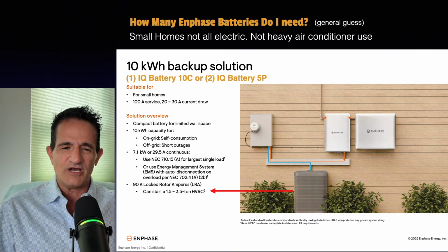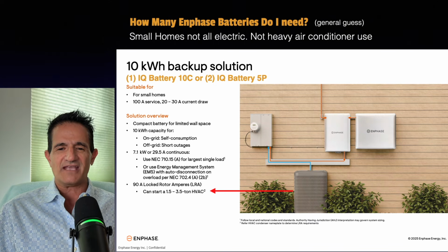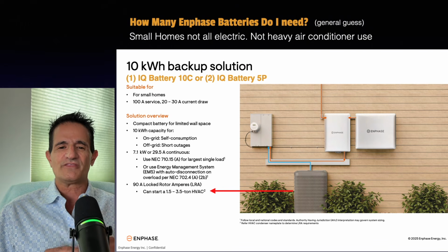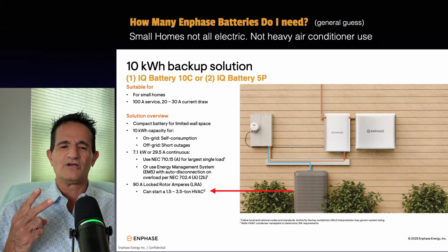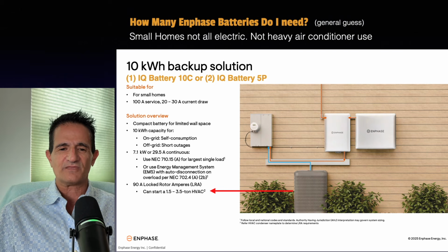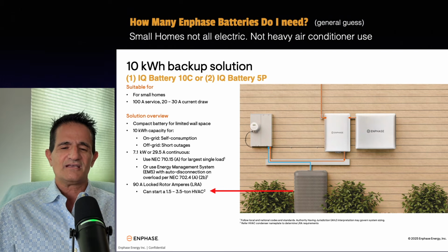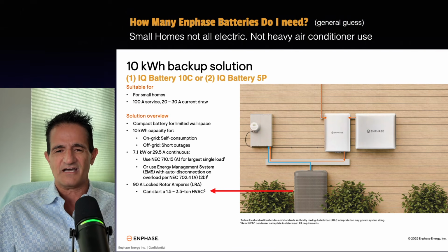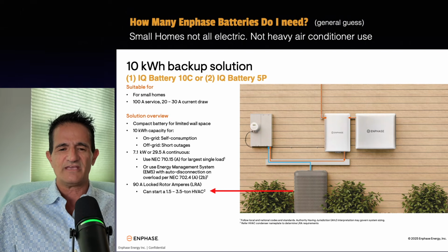But just so I can give you a general idea, instead of just saying I don't know: for small homes, not using a lot of electric, no heavy air conditioner or heat pump use, you can probably get away with one IQ Battery 10C or two of the IQ Battery 5Ps. That will probably be enough, and it will also be enough for a 3.5 ton air conditioner or heat pump in most cases. Again, you have to check the LRA rating.